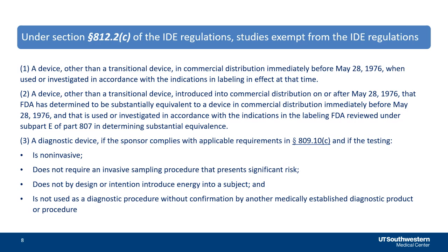and again not approved. Moving forward, diagnostic devices are considered to be exempt from IDE requirements when they are non-invasive, do not require an invasive sampling procedure that presents significant risk, do not by design or intention introduce energy into a subject, and are not used as a diagnostic procedure without confirmation by another medically established diagnostic product or procedure.